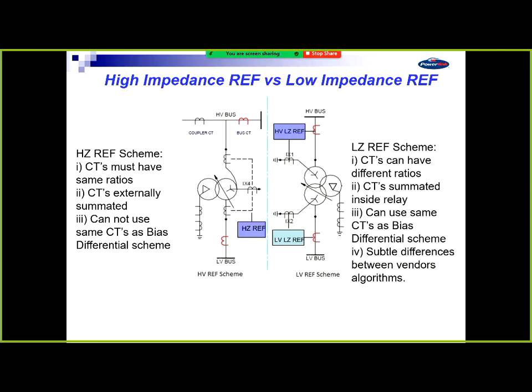When we first changed from the old electromechanical relays, the new electronic style relays replicated what the old electromechanical did. They even went to the extent that a spinning disc takes a bit of time to slow down, so we'll put an algorithm to mimic that. Now, we look at it nowadays and go, why? You want to know the currents drop to zero, why not instantaneously, or 1 millisecond? Why wait 5 milliseconds? It's because the engineers at that time, this was new technology, and this is what we'd been used to for 30 years, this thing you can't do that quickly. That's their mindset.